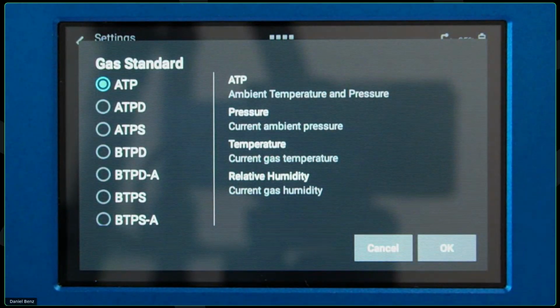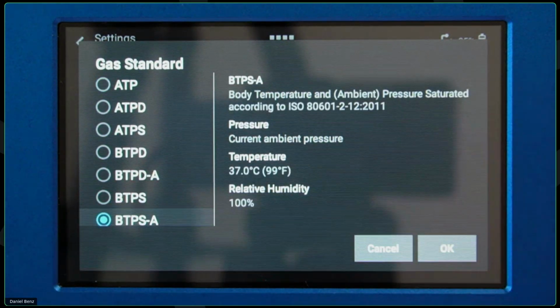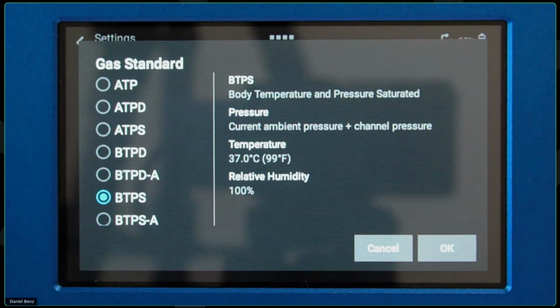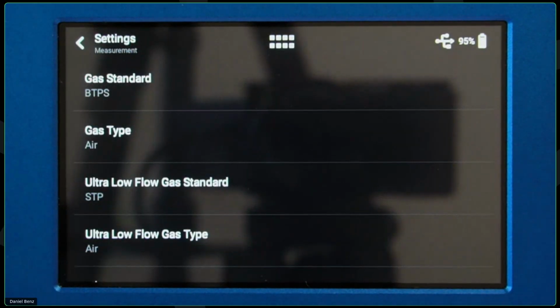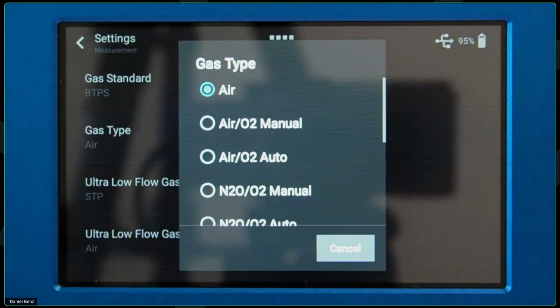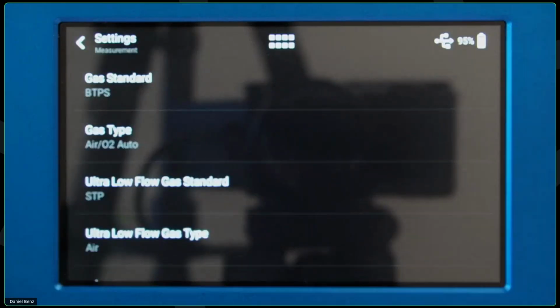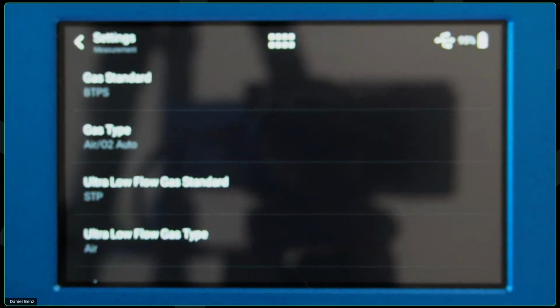The gas standard of the device that I have on test here on my desk, I know from the service manual uses BTPS. So I'm just going to click BTPS here and hit OK. And as gas type, I'm going to select air O2 automatic because I'm going to measure air mainly, but with the automatic, I can actually use the internal O2 sensor to determine the oxygen concentration in my gas mix.